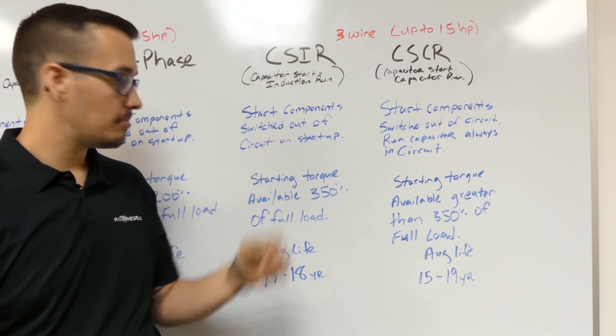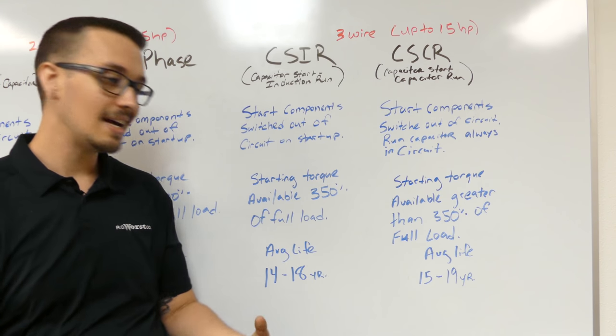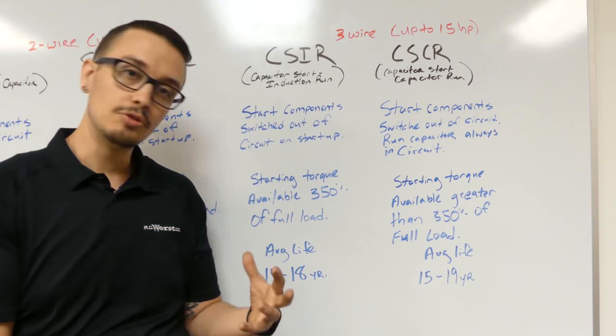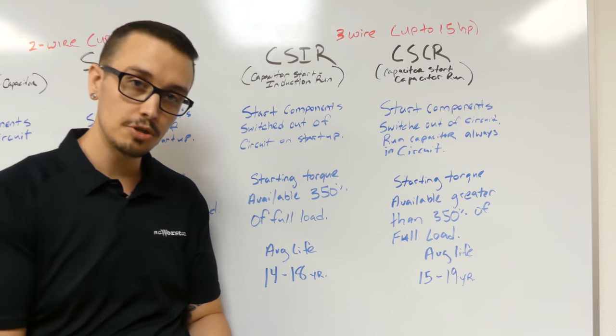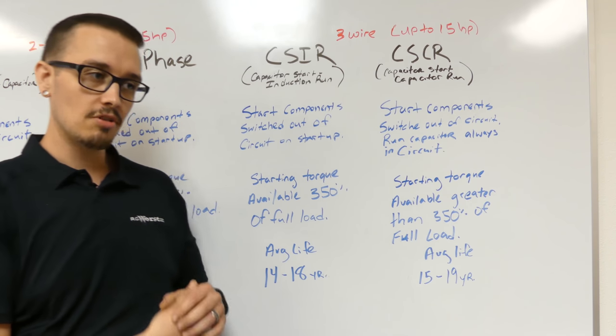So anyways, with the CSIR panel, your starting torque available is about 350% or less of full load. So that's definitely superior to the two wire pumps or motors that we just spoke of. And then the average life is 14 to 18 years generally.